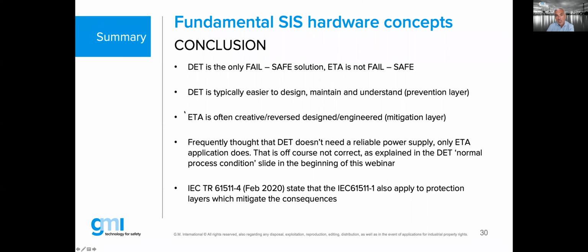Energized to activate is often complex engineered, or reverse engineered, or creatively engineered. And that's why sometimes those types of examples in the industry may be a bit of a difficulty for engineers to understand. Let's say 90% or 95% of all the examples are energized to trip, and those are the simple examples for engineers to understand. Now, if you throw in a few energized to activate, sometimes it is confusing for them.